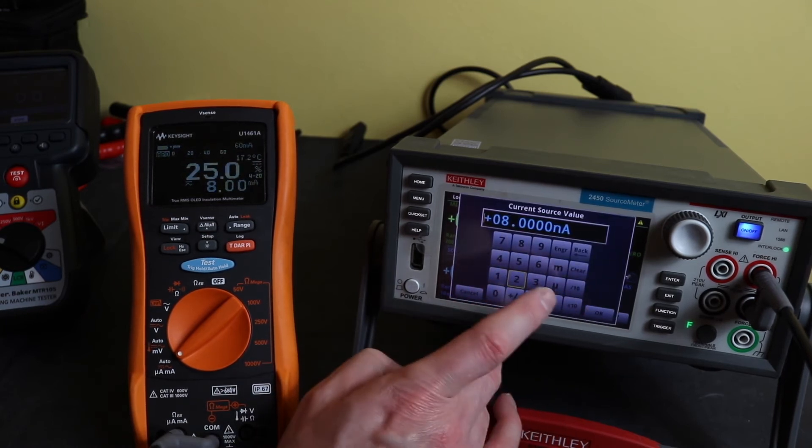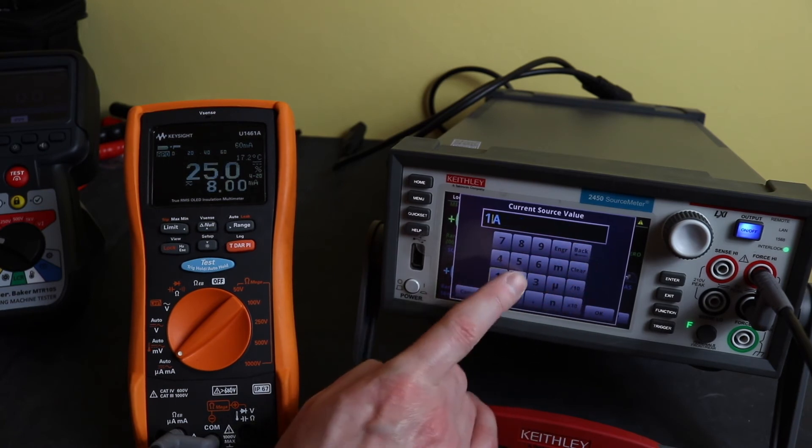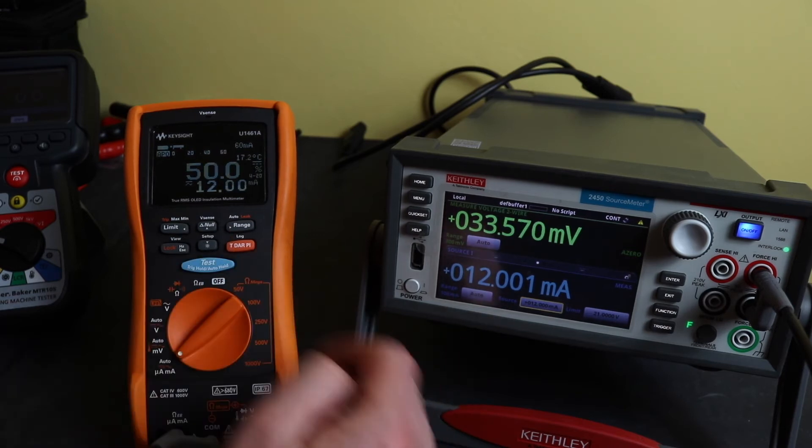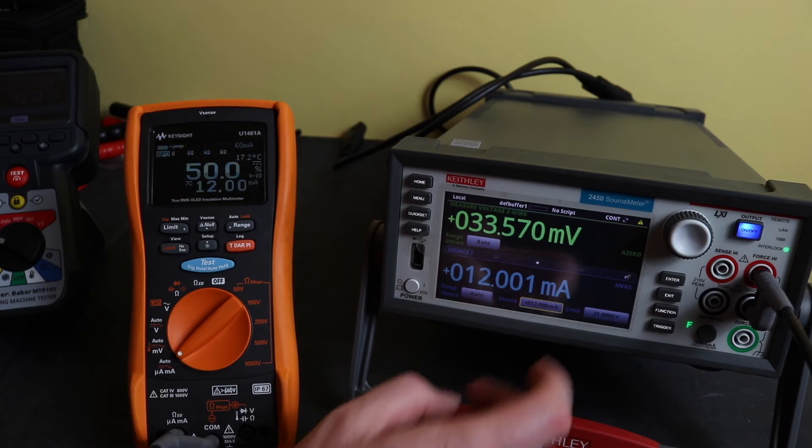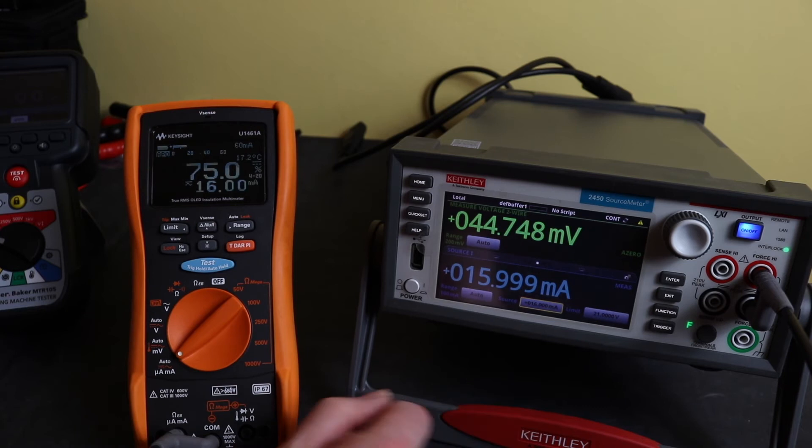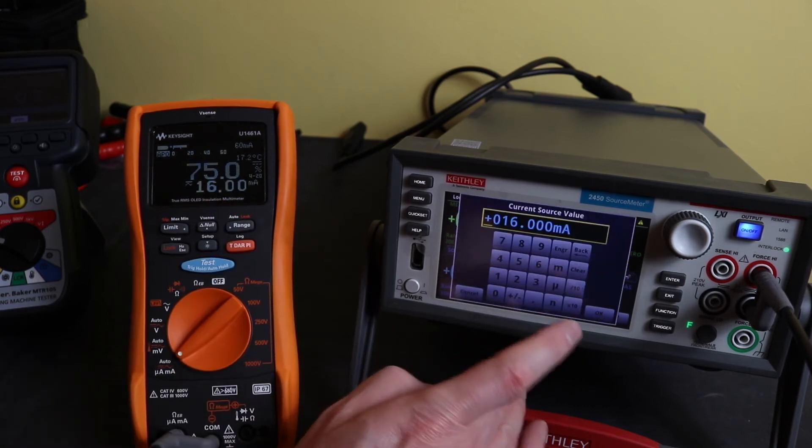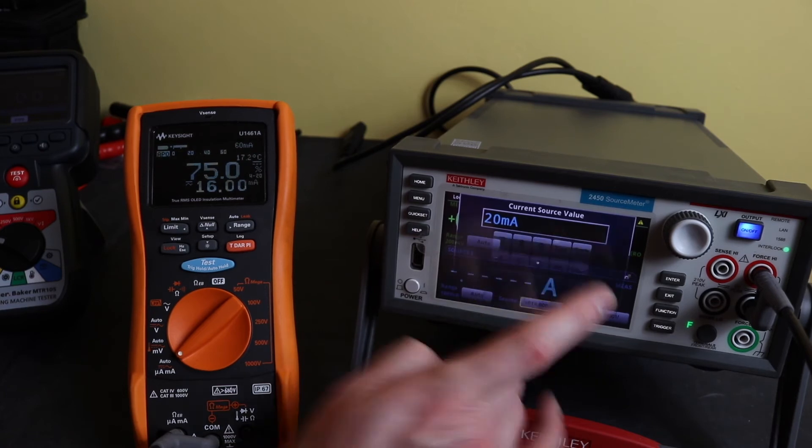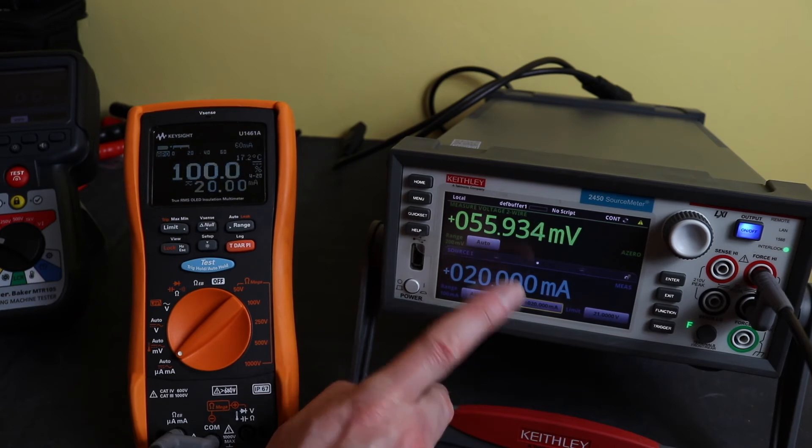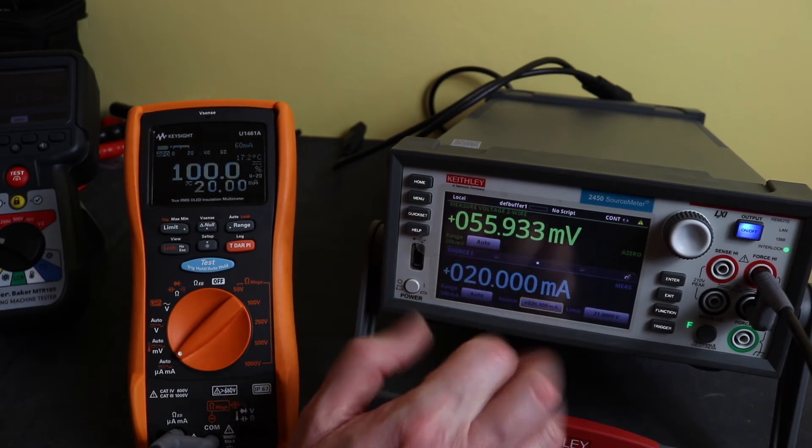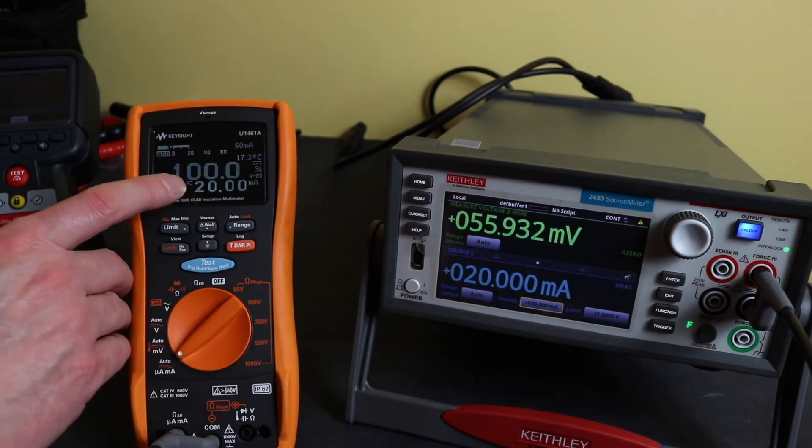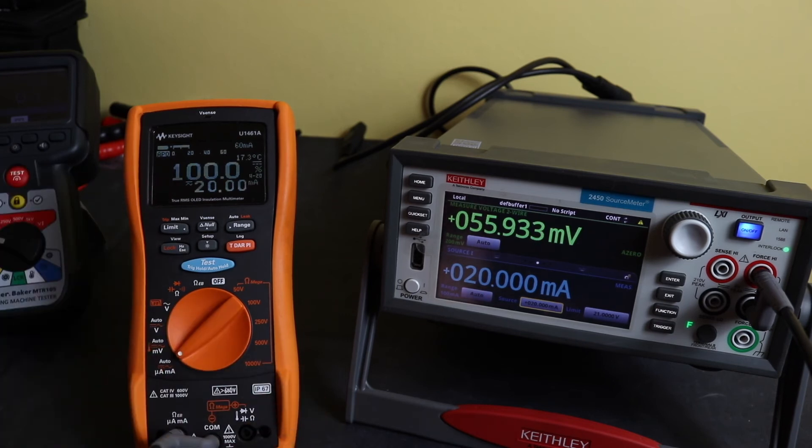Let's go up another four milliamps, 12.001 on 12 there and dead on 50 percent, 16 milliamps 75 percent 16.00 and finally 20 milliamps full range is 20.00 dead on there, 55.93 millivolts there, it's a very low burden and you see on the Keysight here superb accuracy 20.00 milliamps and smack on 100 percent.